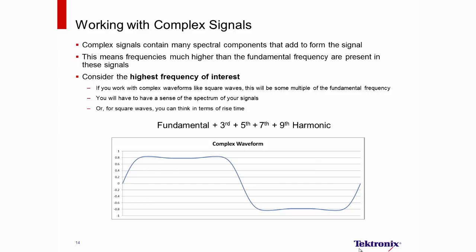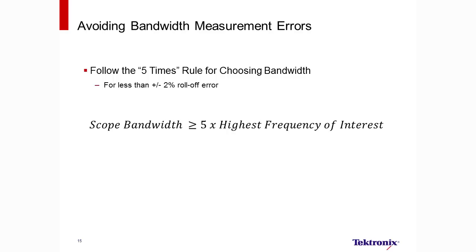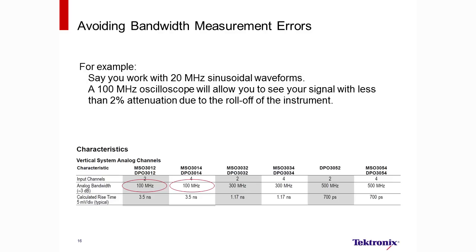So, in general, a higher bandwidth will provide a more accurate reproduction of the signal of interest. Remember when I showed the roll-off curve of a typical scope? I said that the response was pretty flat until we hit one-fifth of the bandwidth. While the actual roll-off of a scope can vary from scope design to scope design, this one-fifth relationship is a good rule of thumb. So, to determine the oscilloscope bandwidth you need to accurately characterize signal amplitude, follow the five times rule. If you choose your scope to have five times the bandwidth of your signals, you should expect less than two percent error due to roll-off. For example, if you're working with 20 megahertz sinusoids, you'll want to choose a 100 megahertz scope to get accurate amplitudes.